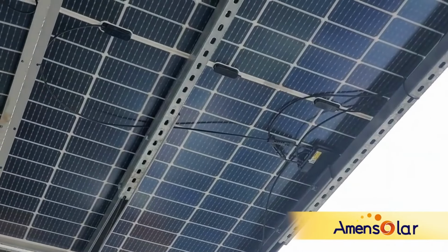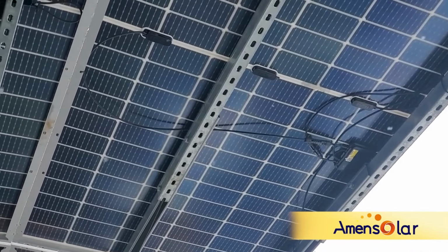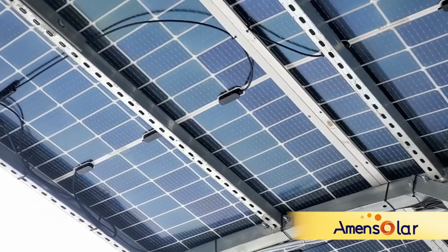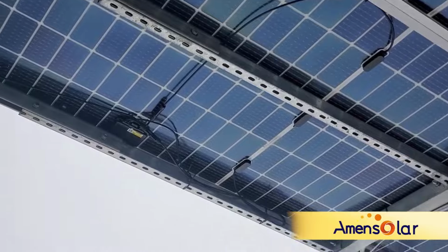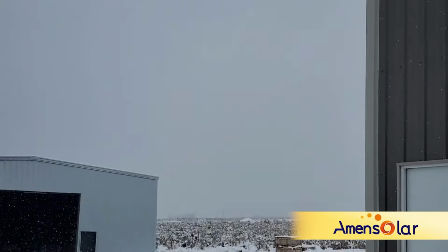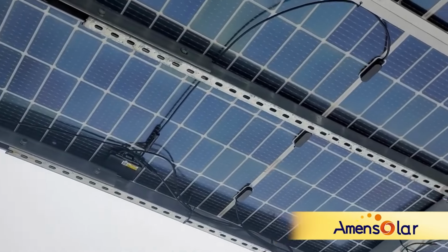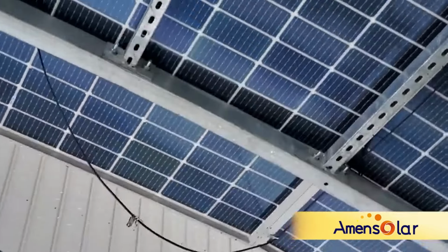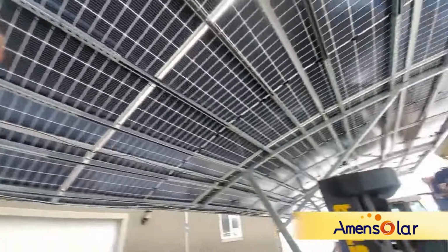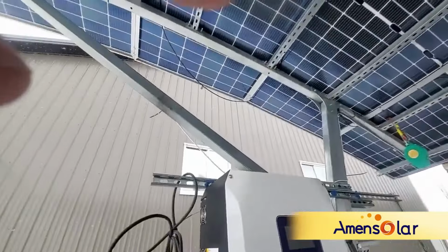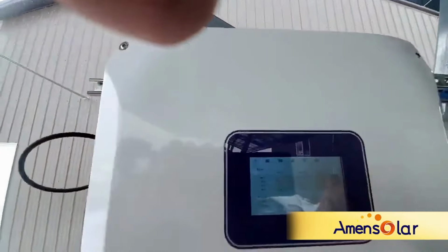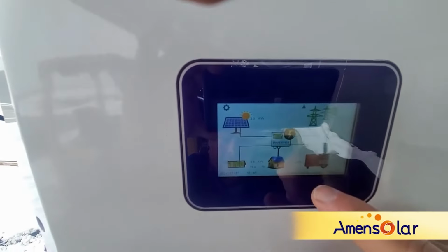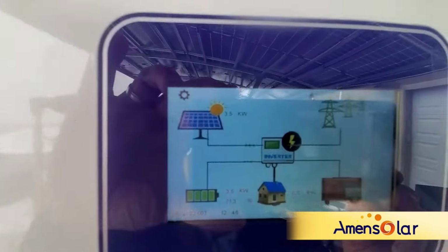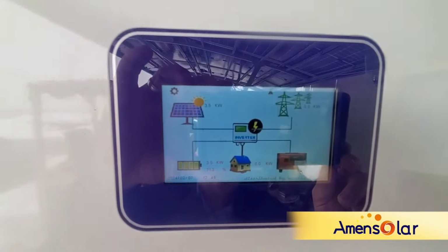Now, as far as noise goes, these Tigos are probably about the noisiest thing. They give a high-pitched whine when they're busy operating, especially in partly cloudy skies like this. You can see it's snowing there right now. Those are whistling like crazy, but the inverter is actually pretty quiet. And out of this 15 kilowatt array today, we are getting, let's see how many watts of solar we're getting. We're getting a total of 3.5 kilowatts. Now this is quite a lot of light here today. So there we can see 3.5 kilowatts. It's busy charging our battery.